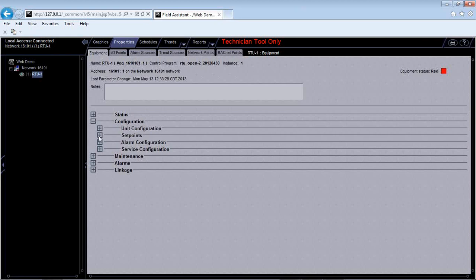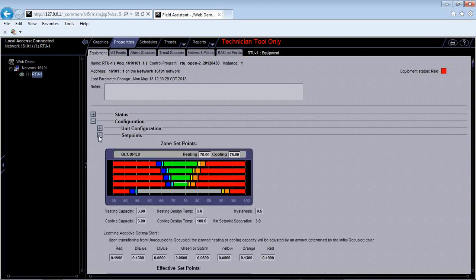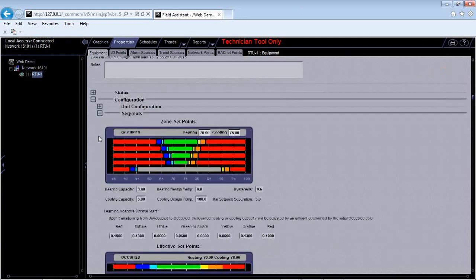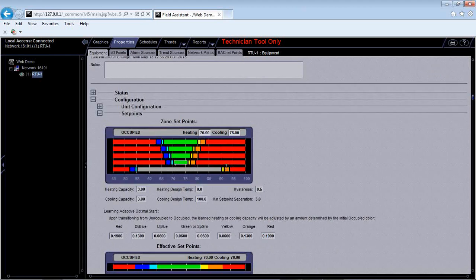So I'm running a little low on time here, so I'm going to go into my set points tab real quick. You can see, like we saw before, Carrier likes to do their set points and space temperature with a color scheme here, okay? So I have green, which is my ideal set point value range, right? So right now I have 60 to 70, I am green. Anything left of that will be dark blue, and then red is an alarm, and anything right of that is yellow, orange, and red is an alarm. So blue is cold, orange is hot. That's the general idea here.